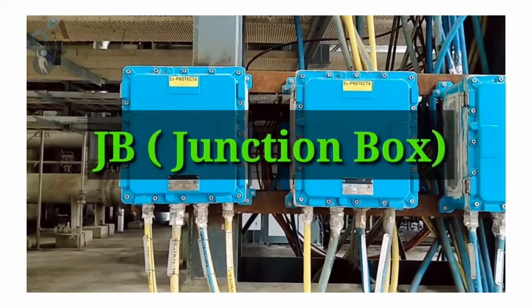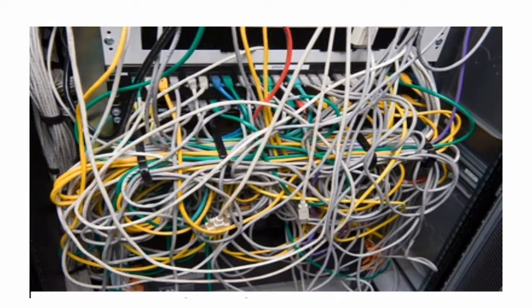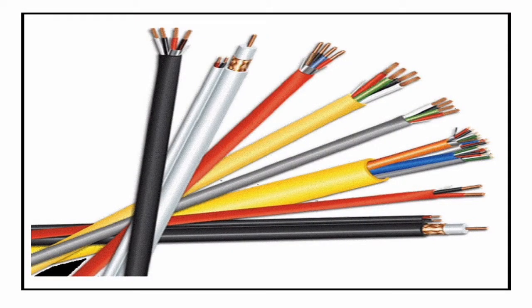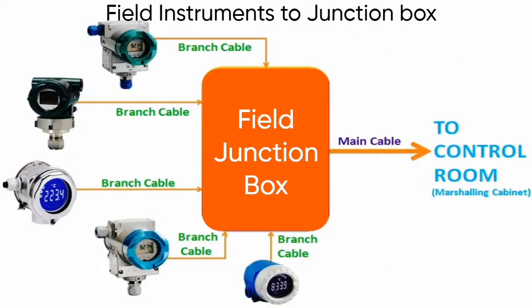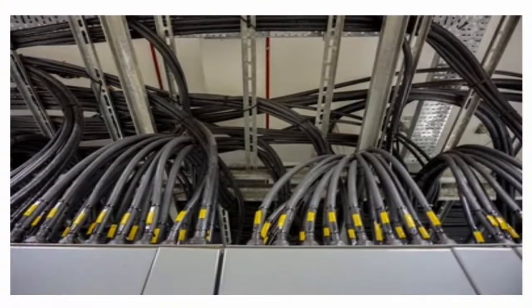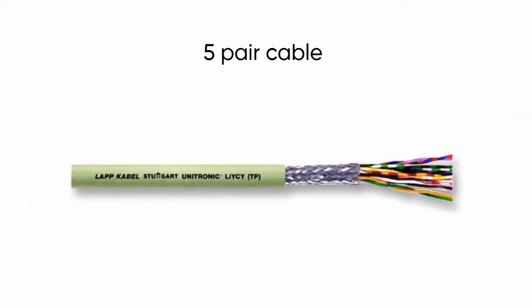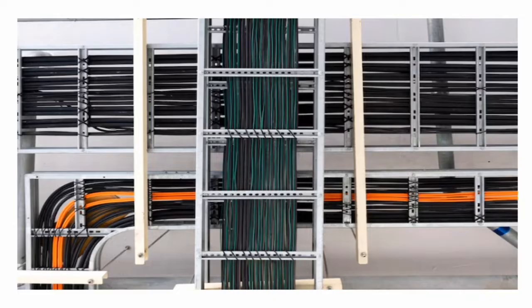Cables used for connecting the field device to the junction box are called branch cables or field cables. Generally, we use one-pair cables for branch cables. Five field devices are connected to a junction box using individual branch cables. For carrying out these five signals to the control room, we need a minimum five-pair cable — meaning one cable has five pairs — and we also have to consider spare cable requirements for future purpose.